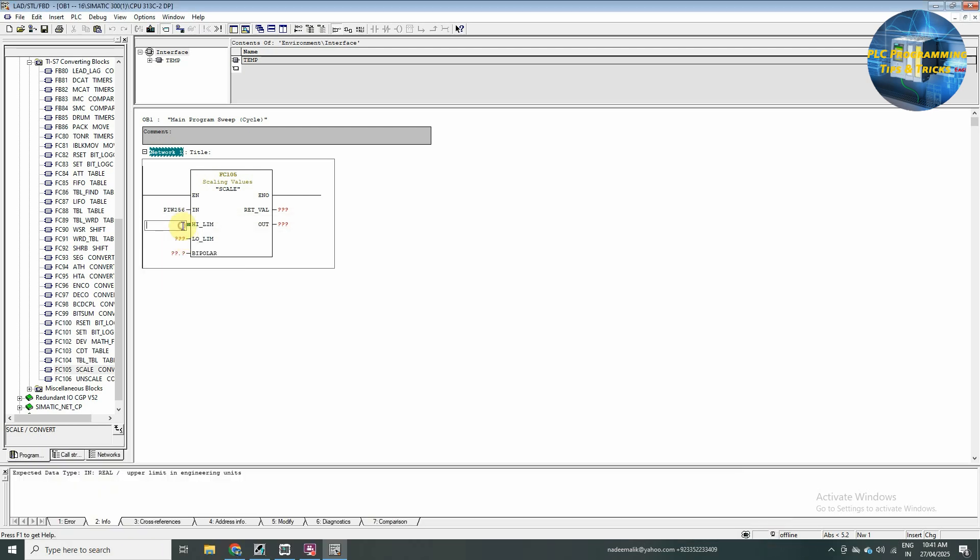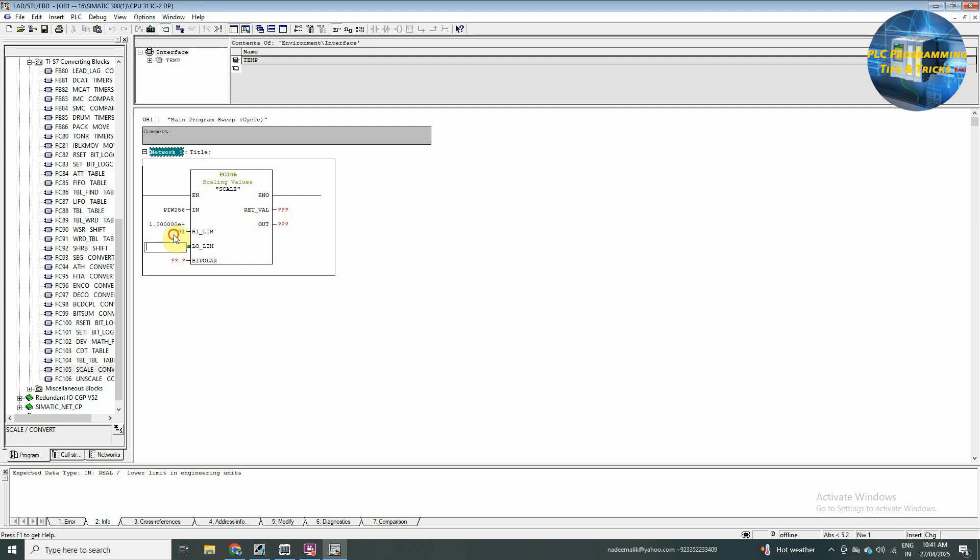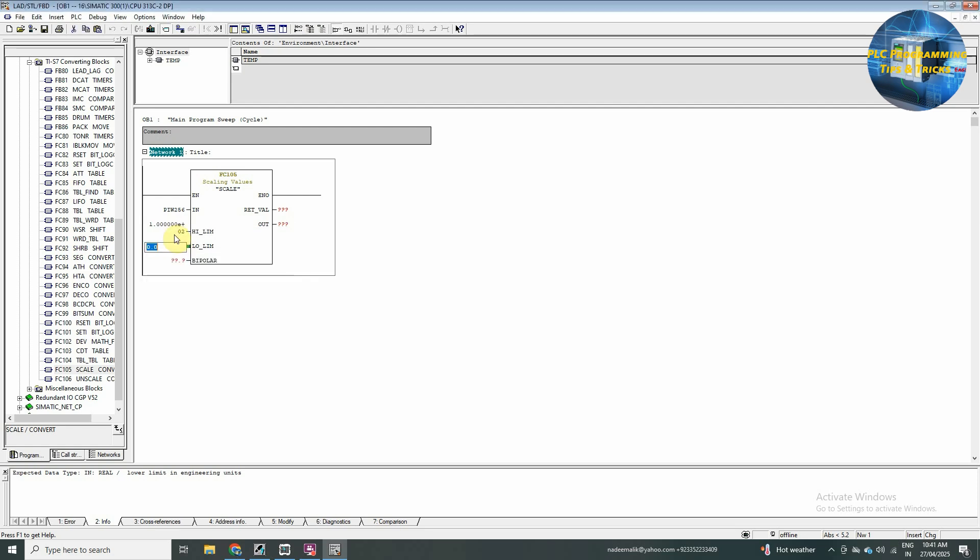Next, we will insert the high limit and the low limit. So, as we are going to convert this PIW 256 analog input to 0 to 100%, we will put 100.0 and for the low limit, 0.0.